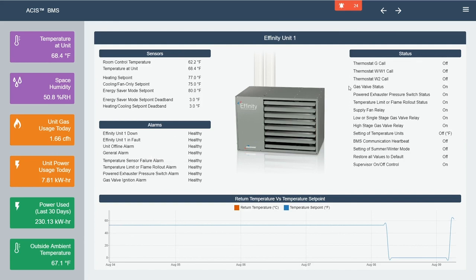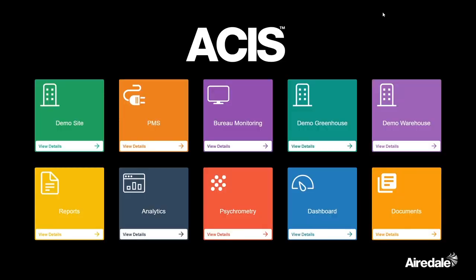But these units are not obviously only used in greenhouses. They're used all over buildings, in warehouses, in loading bays, things like that. So before, these units were never connected into the system. They were always standalone devices out in these areas, and the only way you really knew if you had a problem was if somebody in the space actually came and told you, oh, the temperature's too low, or I'm too cold. But now, because we've integrated this into a BMS system by allowing BACnet or Modbus connectivity, it means that they can get this information straight away.